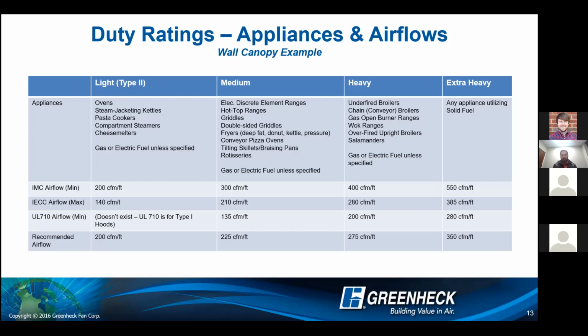So what dictates this? Once you have your appliance lineup, you're going to take a look at the worst case appliance going under that hood. That's going to dictate whether it's a medium, heavy, or extra heavy Type 1 hood. So let's just say that we had an appliance lineup with an oven, 2 fryers, a griddle, and a charbroiler. A pretty standard, I don't know, like Applebee's type appliance lineup. We're going to look at what is the worst case appliance. The worst case appliance is the charbroiler in that particular instance. So that is going to mean that this hood is going to have to be a heavy designation.